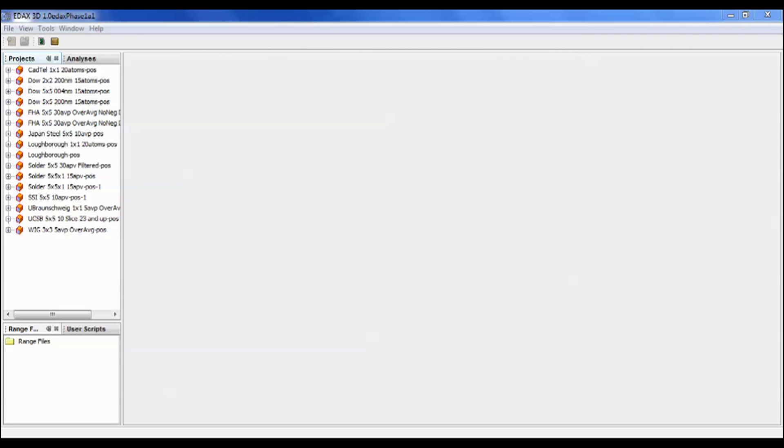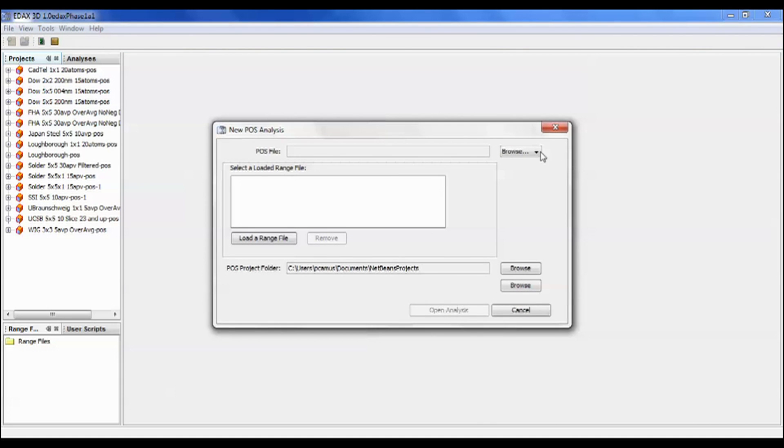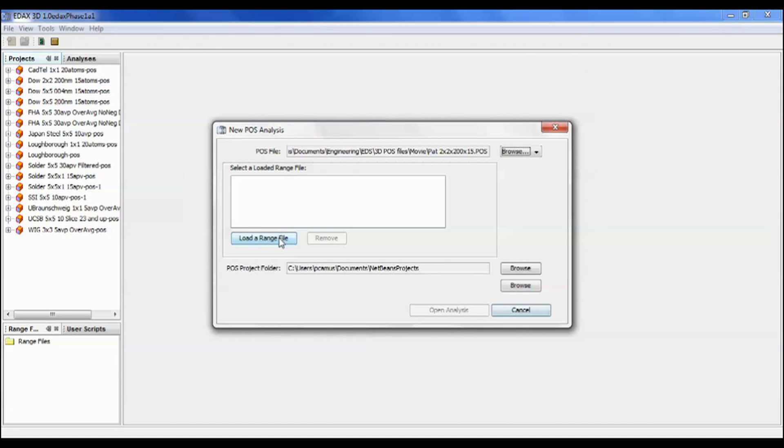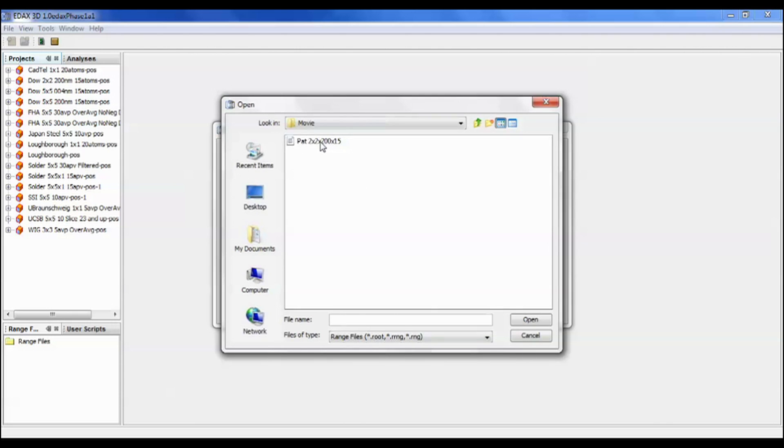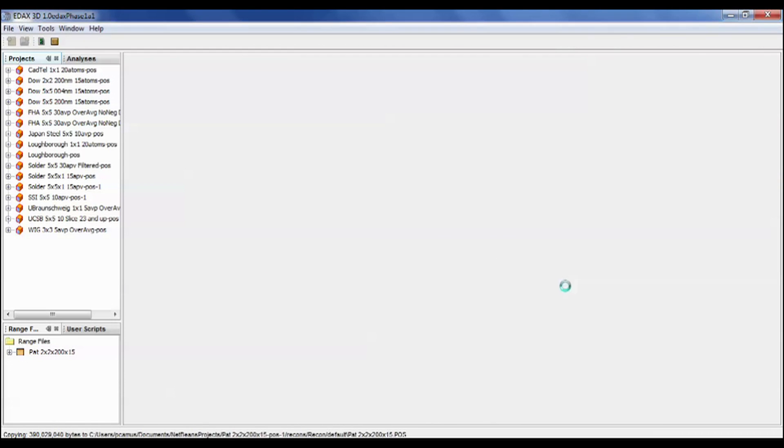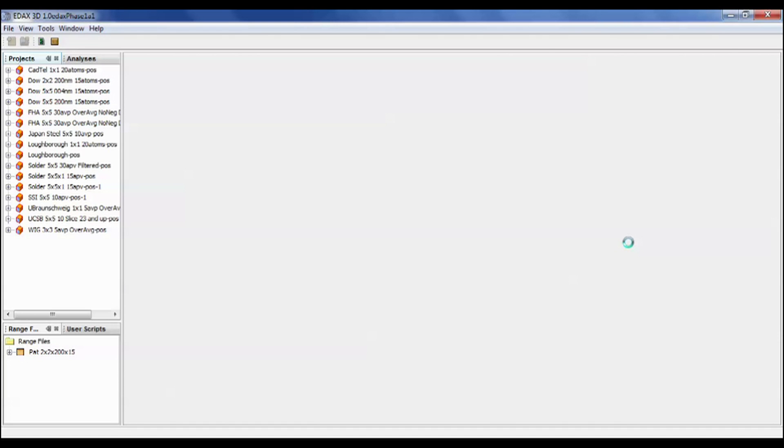So we start the 3DiQ software, go to the file menu, load new POS file. We want to browse to the location that we just saved that POS file from the previous analysis. We need to also include a range file which is defined as a file that defines what the energy range is for each of the elemental x-rays that we are concerned with. We highlight that and open it. It will now open that data file, which is many hundreds of megabytes in size usually, and it will process that filtered according to the range file and then display the x-rays on the screen. Depending upon the speed of your processor and the number of pixels and slices, of course this processing will take longer or shorter amount of time.